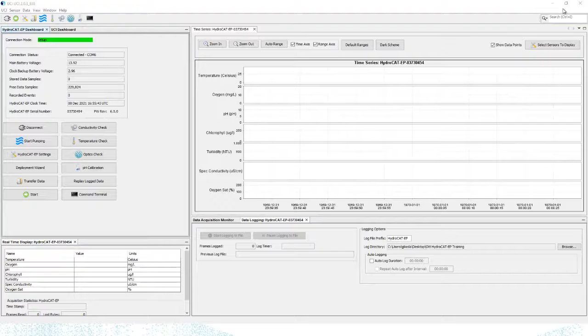So for pre-deployments, you're going to want to do a couple of things. First, run the deployment wizard, that wizard that I demonstrated in UCI just a moment ago. If you're using SDI12, you can also set the SDI12 address and flag, as well as the output string. All that can be done from within the deployment wizard. Before you deploy, install the pH module. If you don't want to get pH data, you can also deploy your HydroCAT EP with this dummy block installed. Obviously, you won't get pH data, but you still will get everything else. So that is an option for you. Don't forget to install the pH module, though, if you want to get pH data.